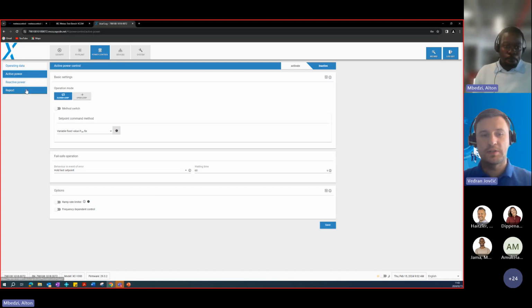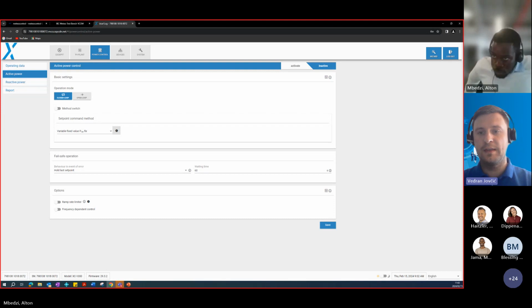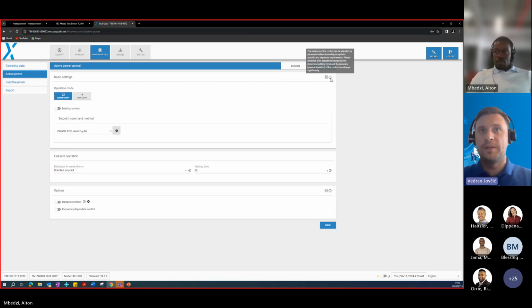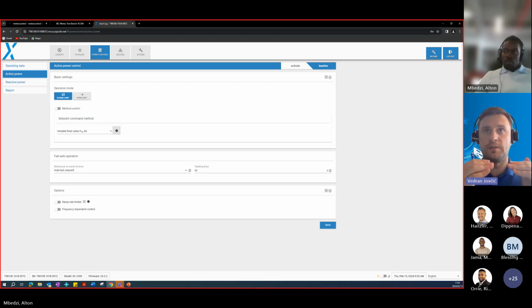And then, just a question — sorry, maybe this is a perfect point to explain open loop and closed loop. I'll explain this very quickly. Closed loop means really having a control loop, so we are regulating the system according to what is happening on the grid connection point, the meter values, and dynamically setting the inverters. Open loop means it's only having one set point, and it's not really important what's happening on the system.